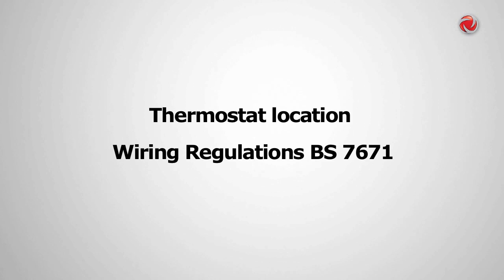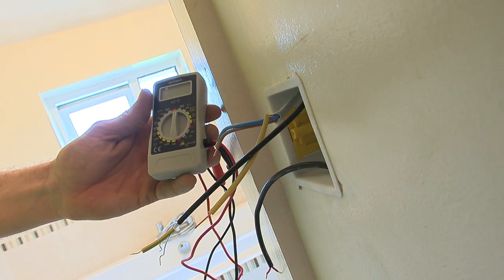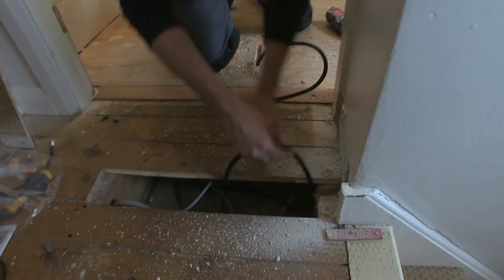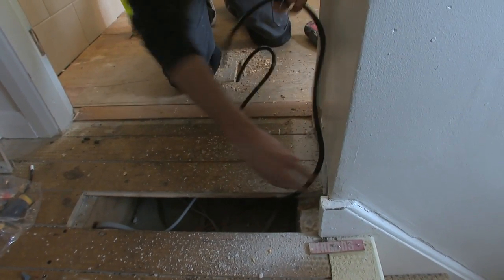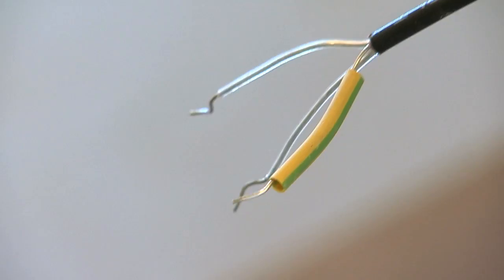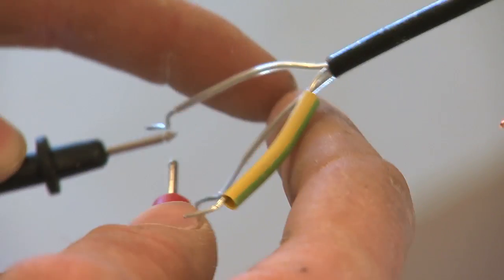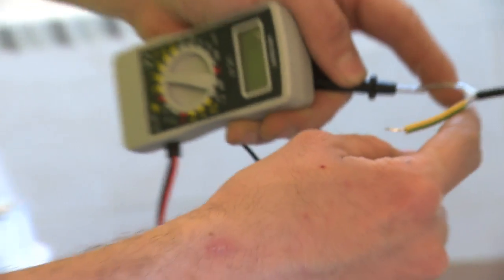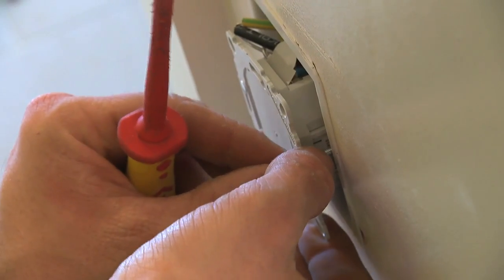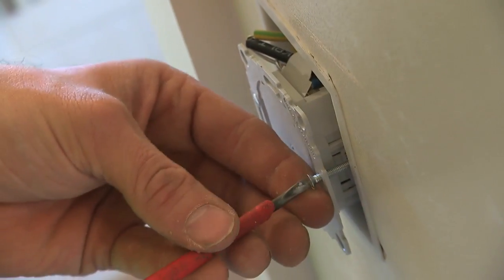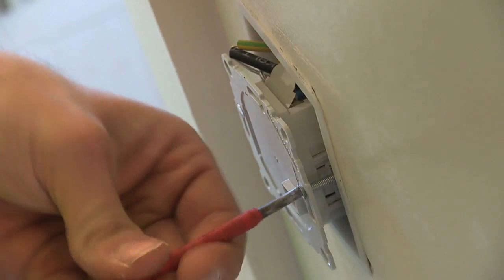All electrical installations must be in accordance with the wiring regulations BS 7671, and therefore the thermostat cannot be located inside the bathroom. The thermostat can be mounted in a standard electrical back box, and the floor sensor can be used to control the room temperature. A standard electrical switch fuse spur with 3mm separation on all poles must be fitted outside the bathroom. We'll show you how to wire this up later in the video.